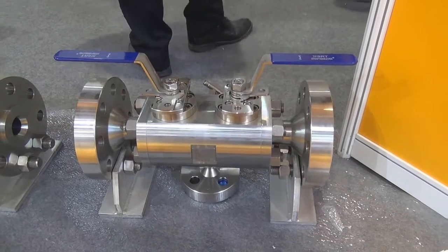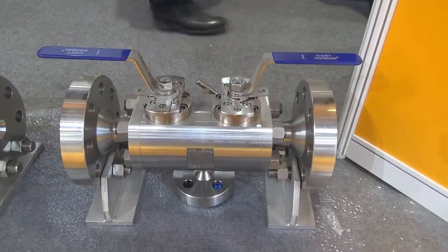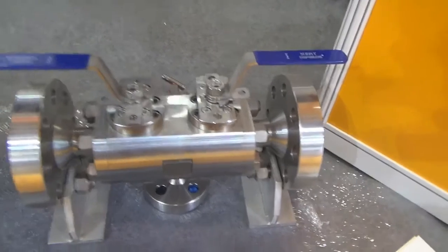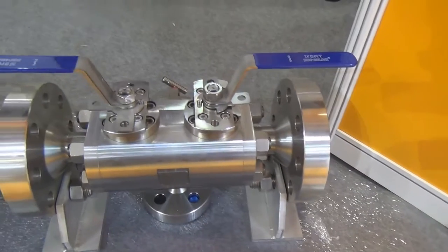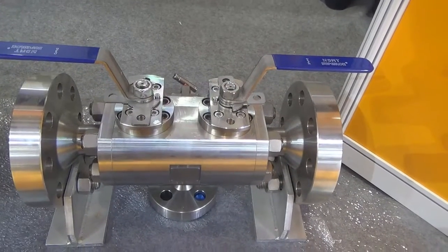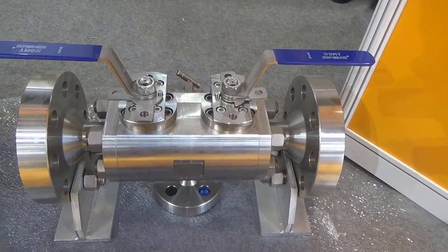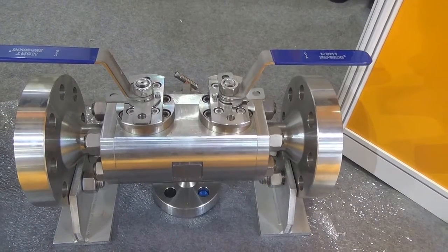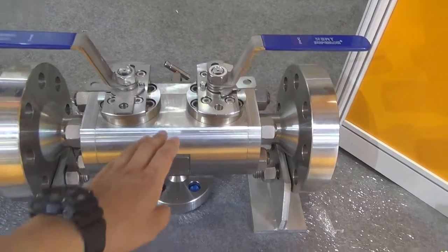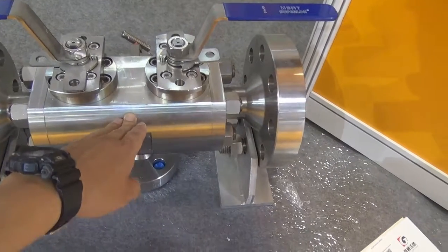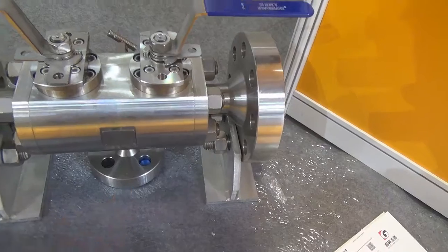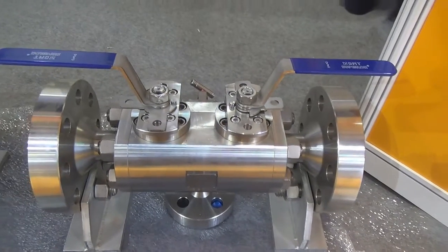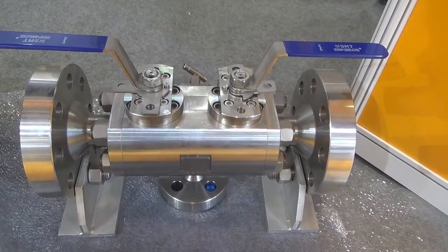Here we have a DBB ball valve. This kind of DBB function comes from two ball valves. This valve body has two balls inside. The reason we designed two balls inside the valve body is that this kind of valve will work in a low temperature environment. When the sensitive flow medium is trapped inside the valve body, we can turn that nut and let the flow medium bleed to the outside. So it's called a double block and bleed ball valve.